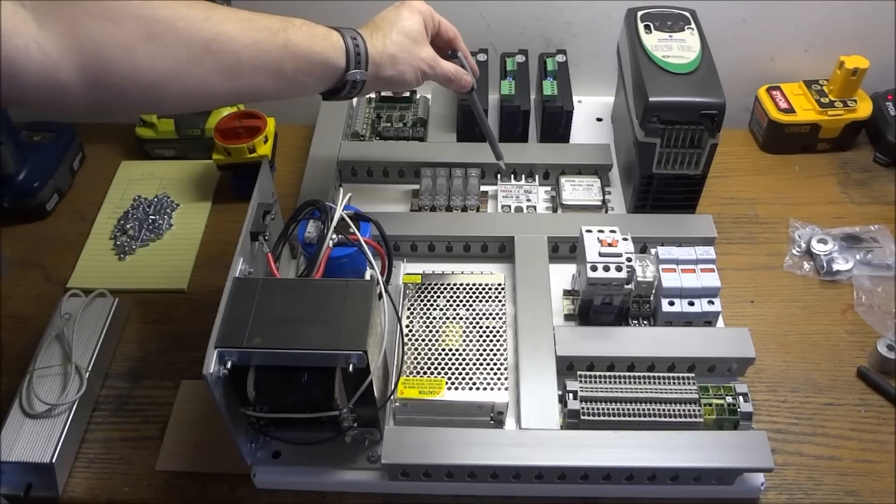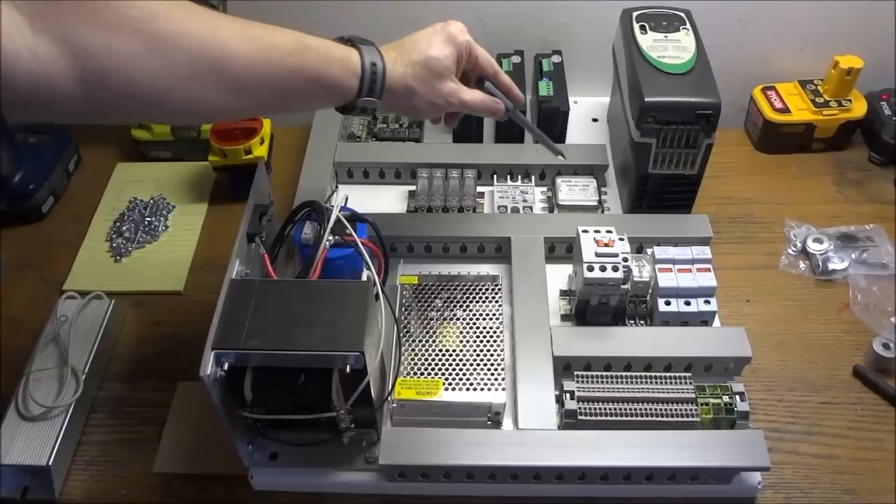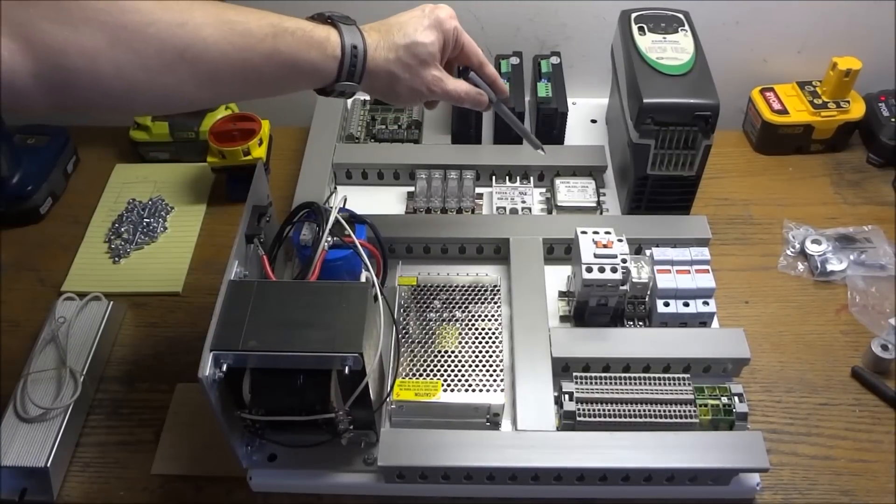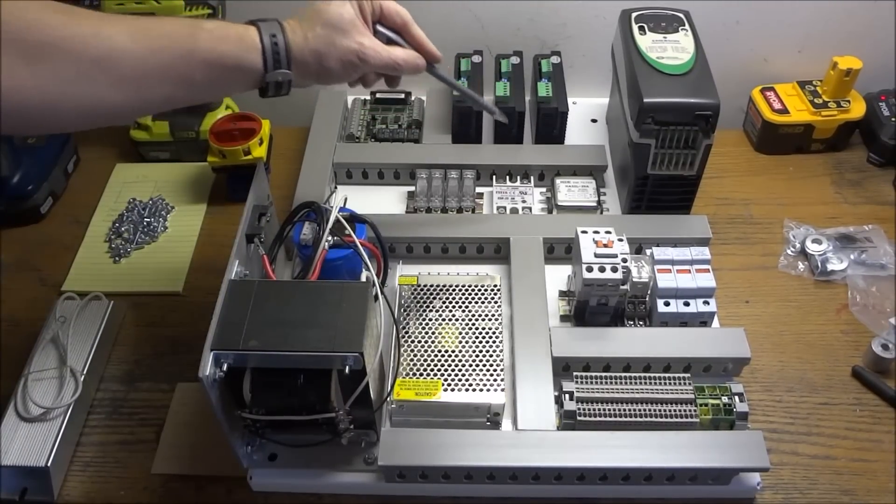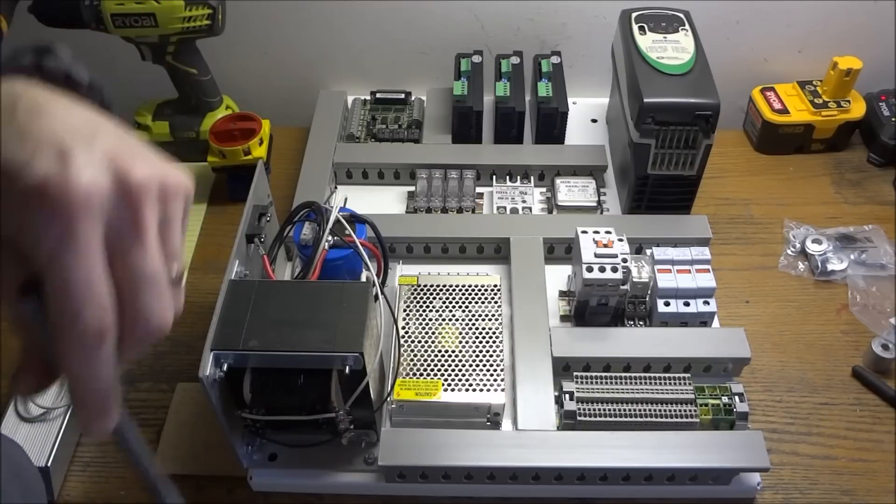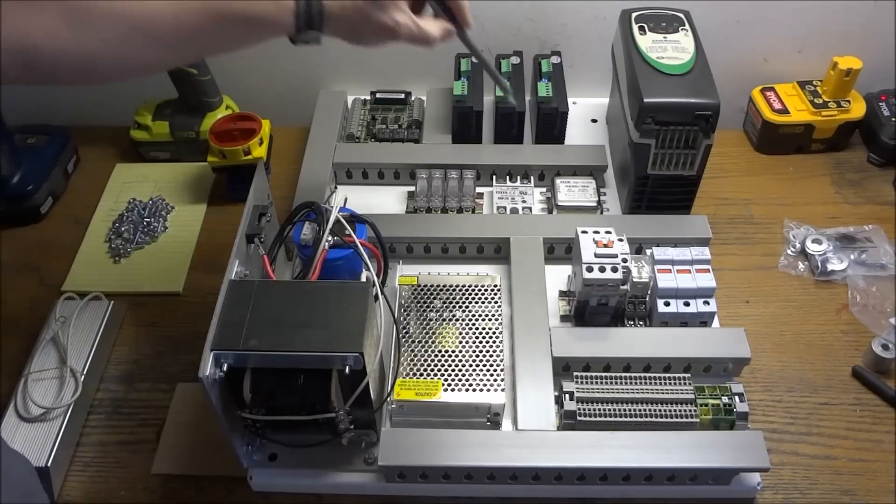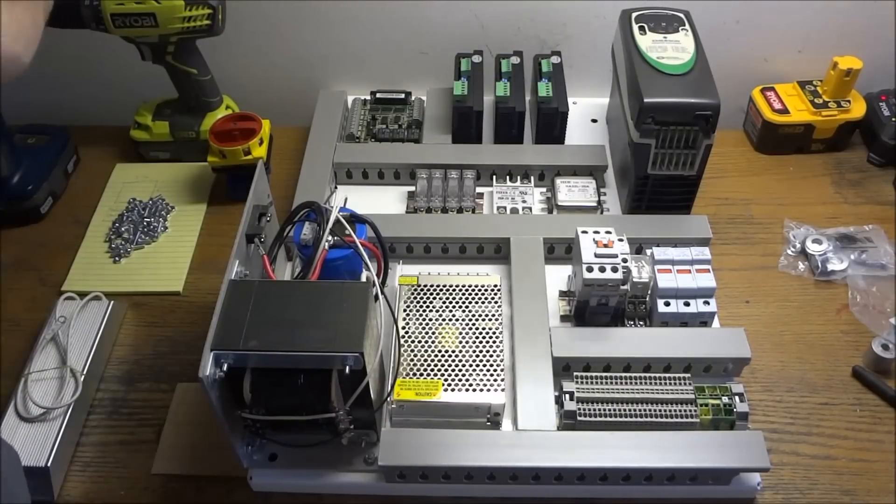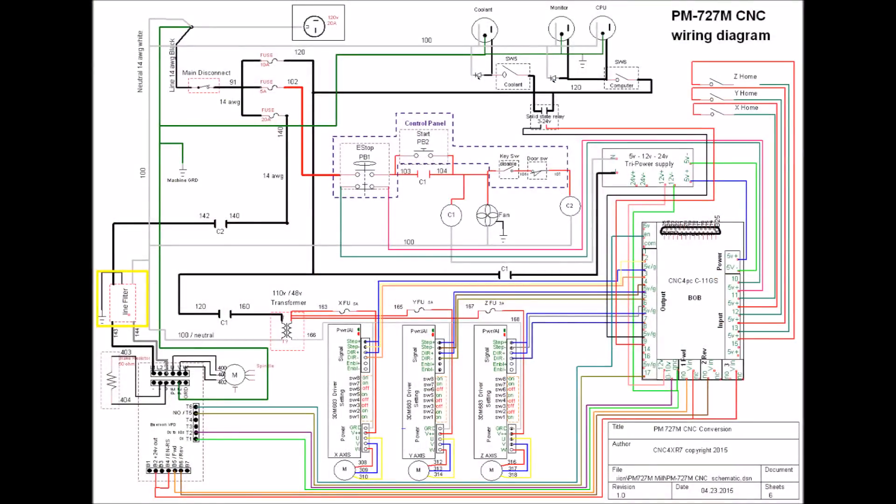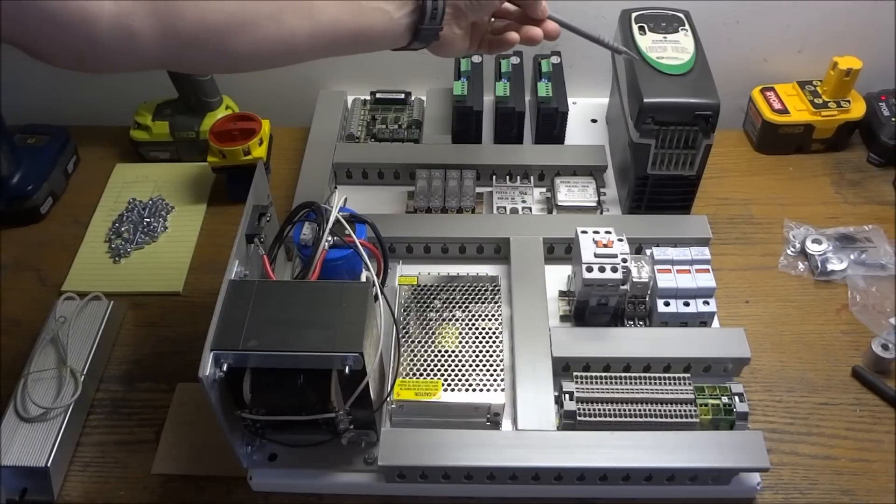Beside our fuses we have a solid state relay. I'm using this relay to turn on my coolant. Next to that we have our EMI filter, and this basically just filters out noise on the power line. This will be in line with the power for our VFD. Now here is the EMI filter drawn on the wiring diagram, and then here on the wiring diagram is our VFD. You can see that the power going into the filter goes from the filter to the VFD.